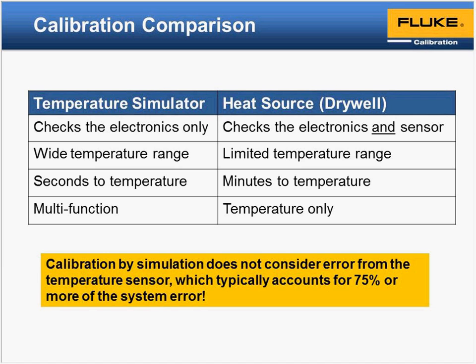Using a heat source, you have to do the electronics and the sensor together. You can be limited by your temperature range, again, of the heat source, and it does take some time to get up to temperature in the source. We're also measuring the temperature of the piece as a system. One big note to remember is if you're doing calibration by simulation, it does not consider the temperature sensor. As we go through the example, you'll see more about that, because we're disconnecting the sensor as we're simulating, calibrating the electronics side. That's the only piece you're doing in that calibration. So we'll go through the do's and don'ts, pros and cons of each.